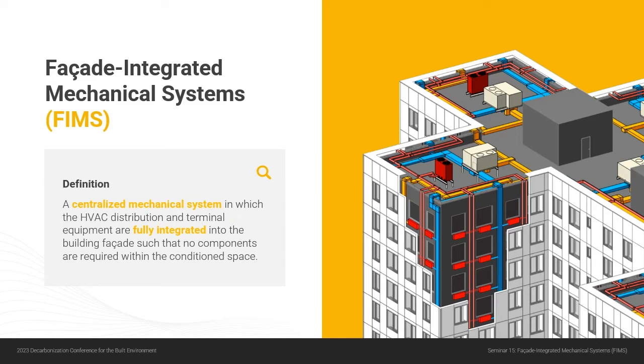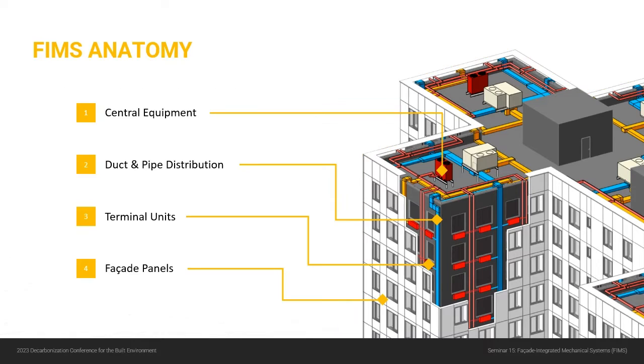So we'll start by defining FIMS: a centralized mechanical system in which the HVAC distribution and terminal equipment are fully integrated into the building facade such that no components are required within the conditioned space. We certainly have made this point enough already, but the point of this is to make this non-invasive. So this is a mechanical system retrofit that can be installed from the exterior of the building, non-invasively. No components required in the space.